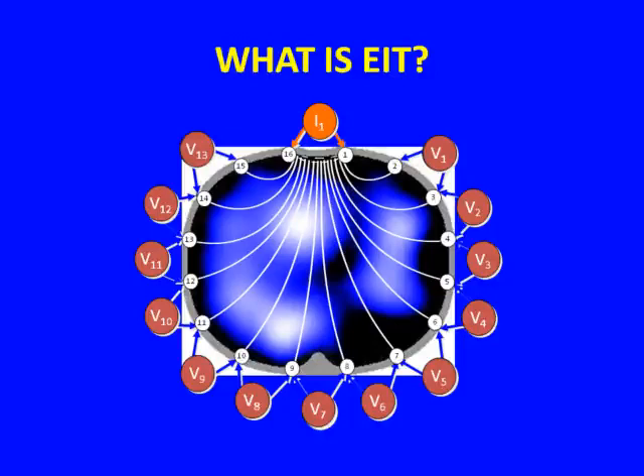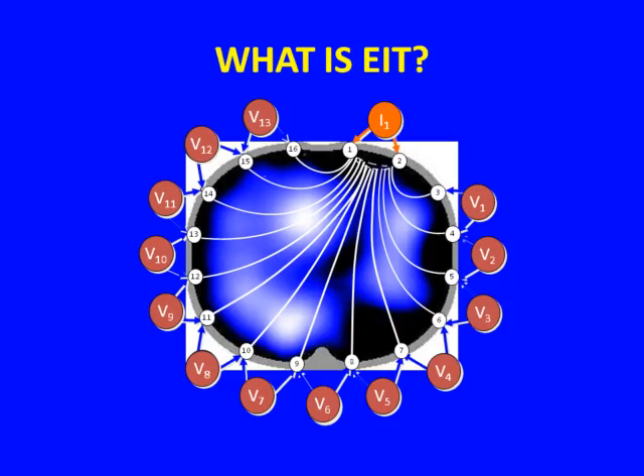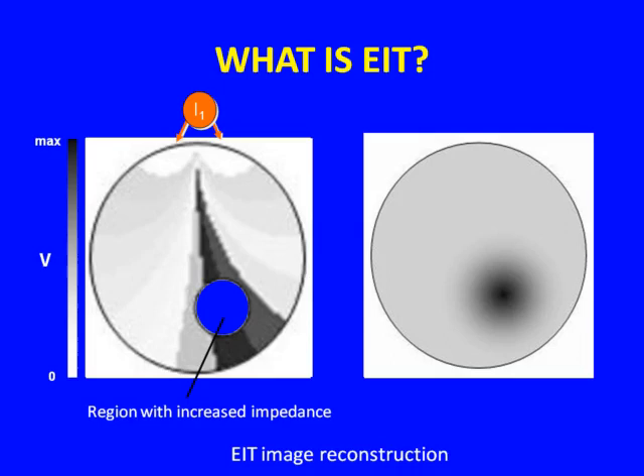Basically, if you have the first current applied to two electrodes, the others will get a signal based on the impedance of what is contained in the thorax. Then the current is switched from one couple of electrodes to another, and the signal is registered again from the rest of the electrodes. So if you have a region with increased impedance inside the field of view of the electrode belt, a set of currents will pass through and identify this region.